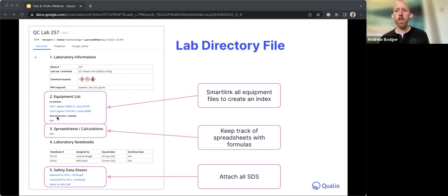Maybe I'm not fully thinking it through, but there could be a way that you could potentially use tags for it, because tags can be added and removed at any time. So if you're labeling them with the PM, maybe the last service was a PM and you apply the PM label to the various equipment, or when it goes through calibration, you put in the calibration tag and remove the PM. Now you're getting an idea of what was the last service performed on that. It will require you, of course, to make sure that you're managing those tags appropriately. Yeah, that's a good idea. That's at least a workaround that you can do currently to have some way of tracking that.